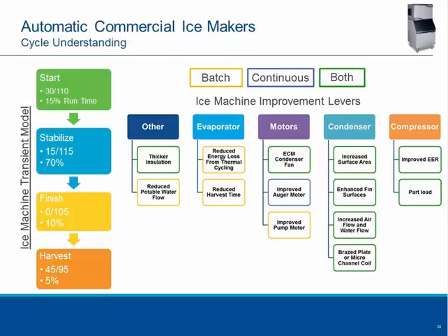This shows the conditions that the compressor in a batch ice machine exhibits during the ice-making cycle. It starts at the start of the cycle when warm water is brought into an ice machine. The compressor is typically running at 30 degrees Fahrenheit evaporator temperature, and if the machine's sitting in a 90-degree ambient, which is where we test these ice machines for rating them, you'll typically see a saturated condensing temperature of 110 degrees.